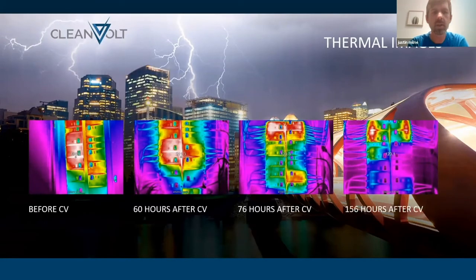Here are some thermal images that were provided to us by a customer that operated a dairy barn. This was located out of South Dakota, so these are US heat numbers, thank God. They're not 186.5 degrees Celsius, that's a good thing. But they were running about 77 degrees Celsius in the before CleanVolt picture on your far left. CleanVolt was installed near the bottom of this bus on the breaker you can see in the second picture from the left. It's starting to heat up green on the bottom. It's sort of cut off in the picture.